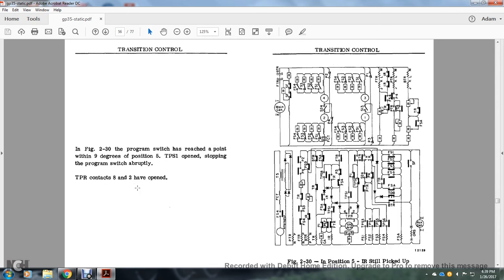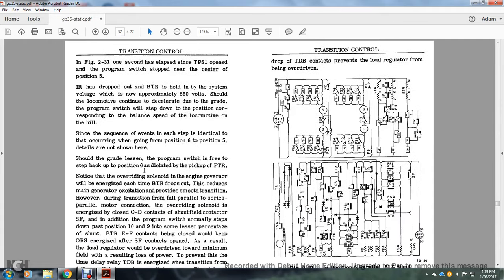Alright, in figure 30, the program switch has reached a point 9 degrees from position 5. The transition power switch is open, stopping the program switch abruptly. Transition power relay contacts 8 and 2 have opened. In figure 31, 1 second has elapsed since the transition power switch opened. The program switch has stopped near the center of position 5. The interrupting relay dropped out with the back transition relay held by the system voltage of approximately 850 volts. Should the locomotive continue to decelerate due to the grade, the program switch will step down to a position corresponding to the balance of speed of the locomotive on the hill.